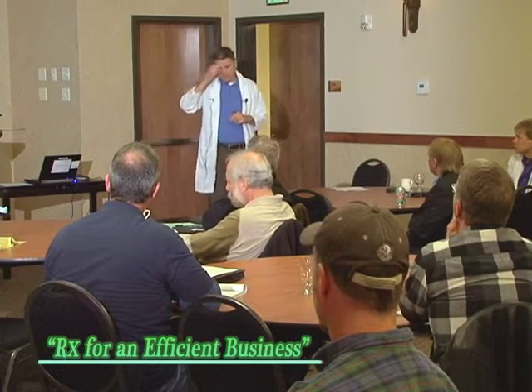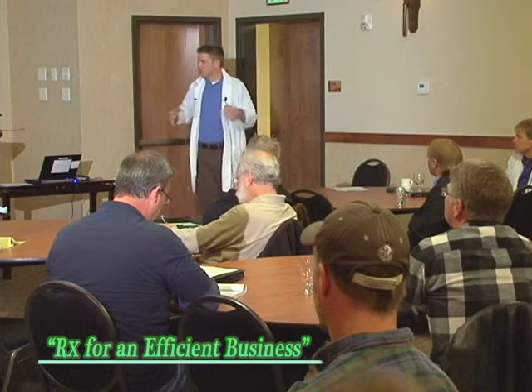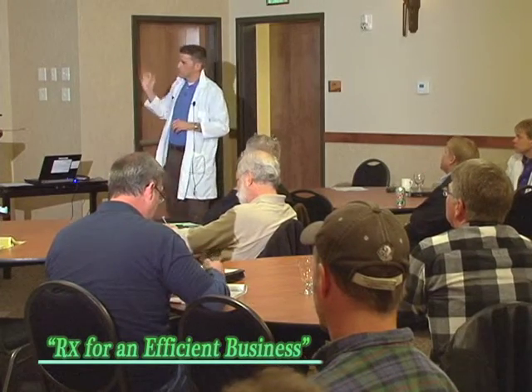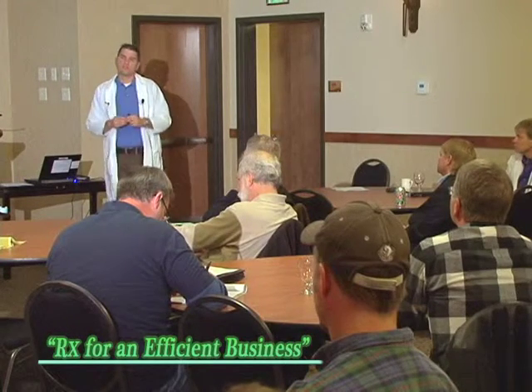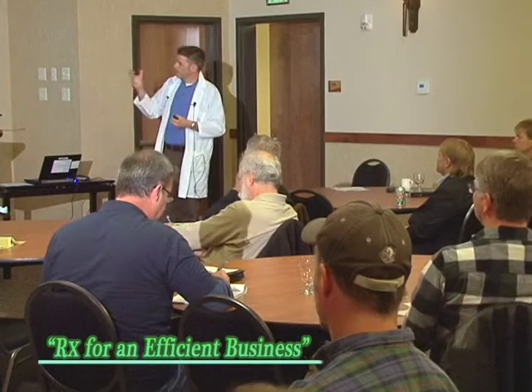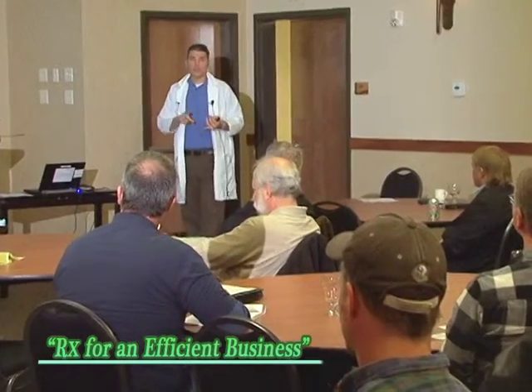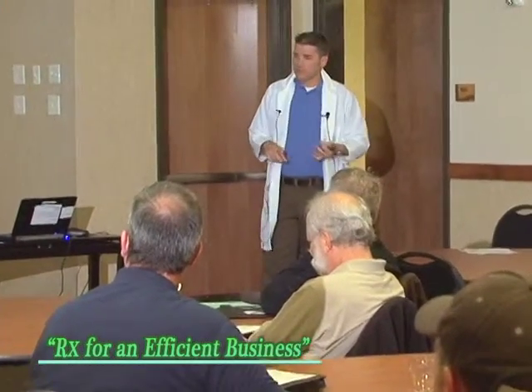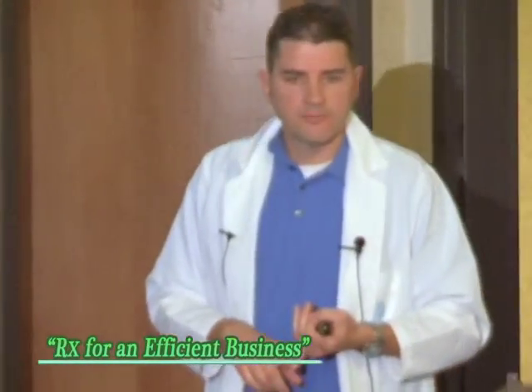John mentioned this in his presentation: are they looking out for your energy efficiency? Of everything I've told you here in the last 20 minutes, ask them, are my systems running as energy efficient as possible? Replacing filters is good. Are they checking the cleanliness of the coils? Are the condenser coils clean and the evaporator coils clean? The tension belts are good. Have they checked the refrigerant charge in a while?